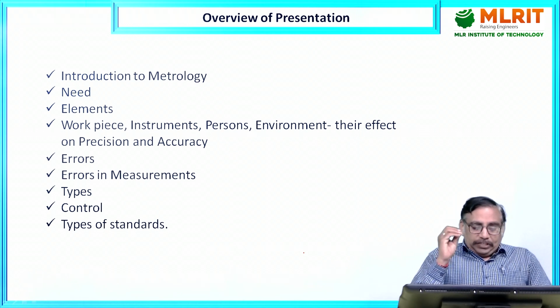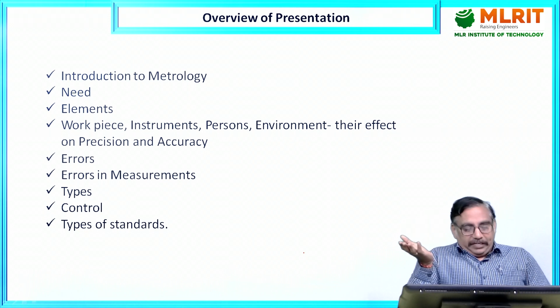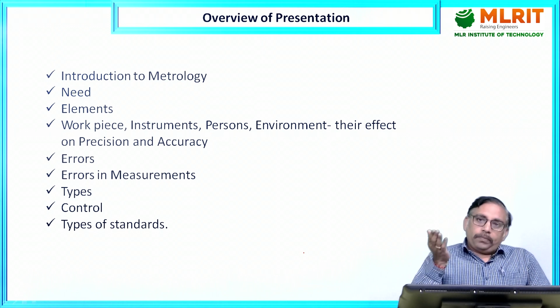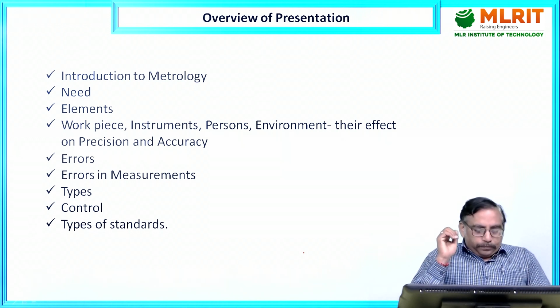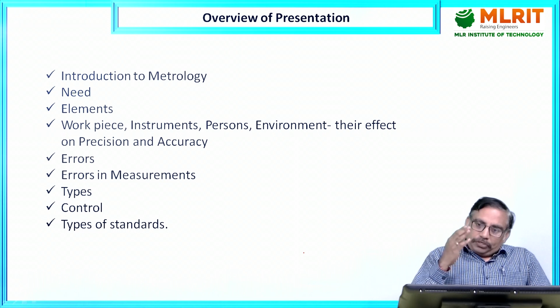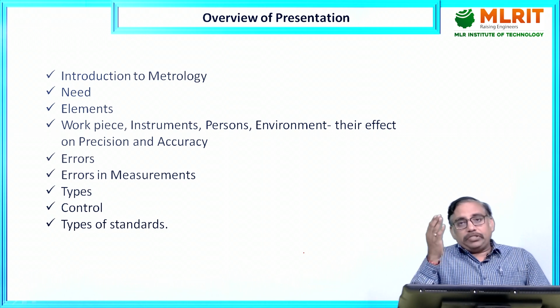So, it will ensure that all measurements carried out are accepted nationally and or internationally, depending upon the usage of the equipment at a particular environment or by a particular human interface. So, calibration is the process of establishing a link between the values indicated by a measuring instrument or measuring system under certain conditions and values obtained by a measuring instrument and corresponding measured values.